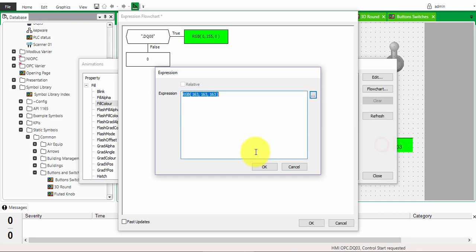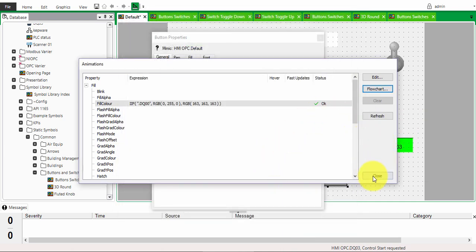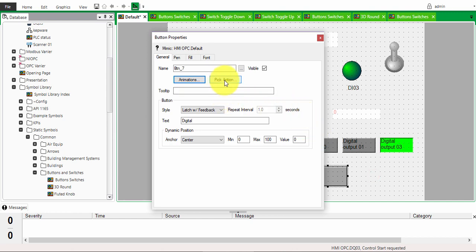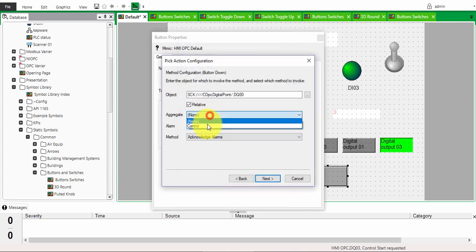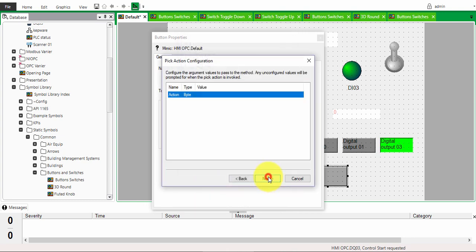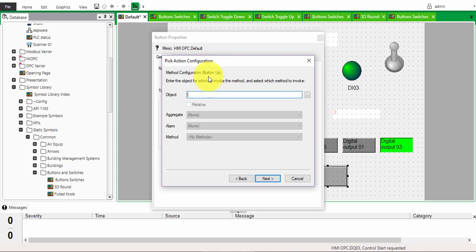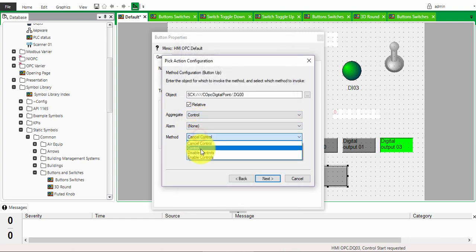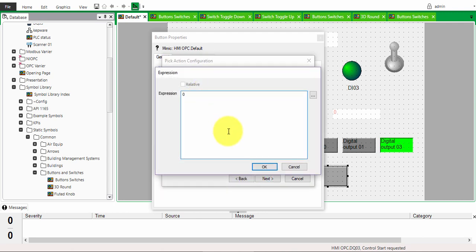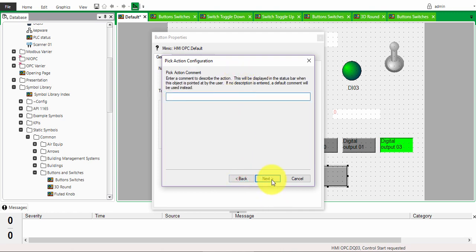Set a shade of gray for off and click OK. For the pick action, choose a method. With latch you have a configuration for when the button is down and when the button is up. When the button is pressed down, choose control and give a value of 1. Click next — now configure when the button is up: choose the same tag, control, and set value to 0. Click next, add any comments if needed, and finish.